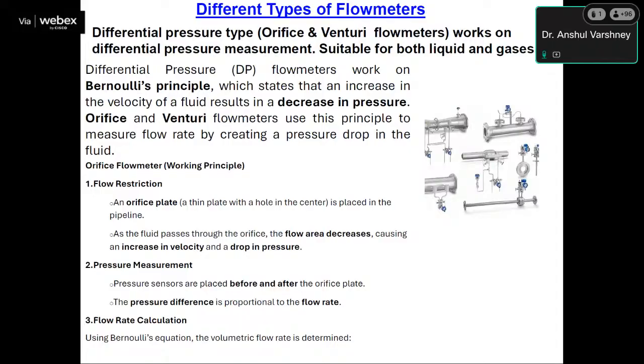Next, orifice and venturi meters. These types of flow meters are known as differential pressure flow meters, and they work on Bernoulli's principle, which states that an increase in the velocity of a fluid results in a decrease in pressure. Orifice and venturi flow meters use this principle to measure flow rate by creating a pressure drop in the fluid.